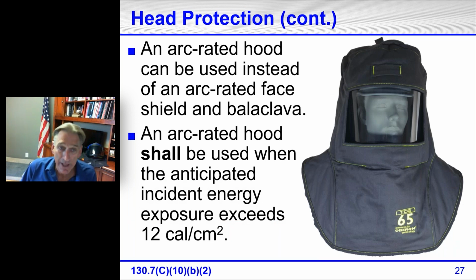An arc-rated hood can be used instead of an arc-rated face shield and balaclava. An arc-rated hood has to be used when the anticipated incident energy exceeds 12 calories. All right, here's Oberon's 65 calorie arc flash suit, the hood and the whole suit. They have clothing that goes all the way up to an arc flash suit of 140 calories.